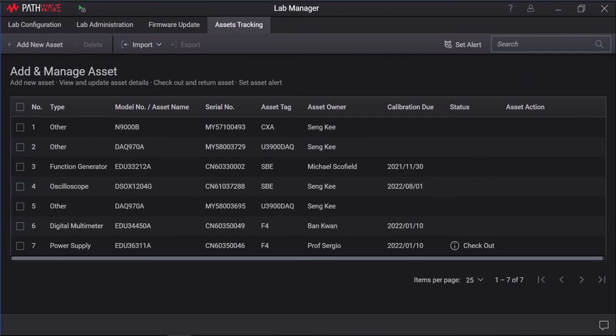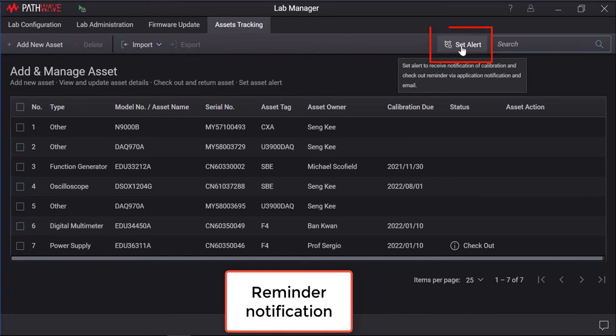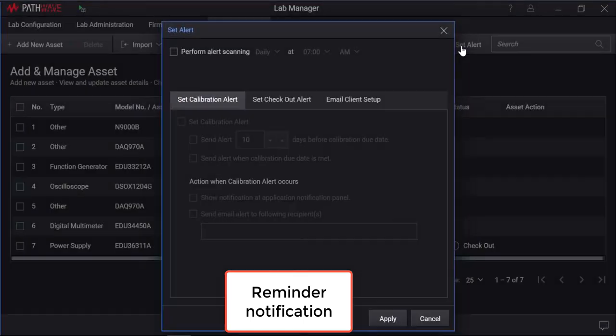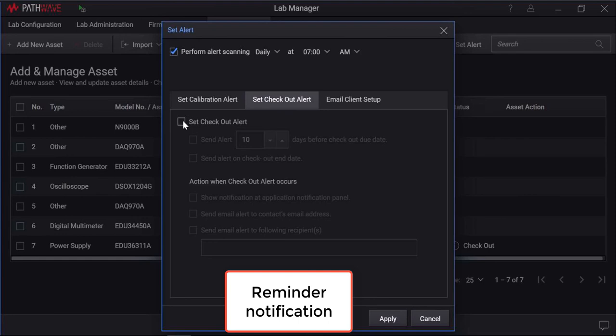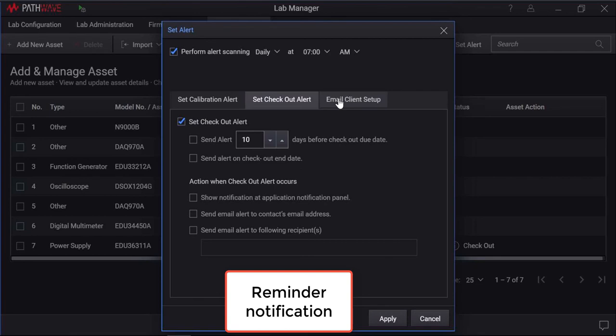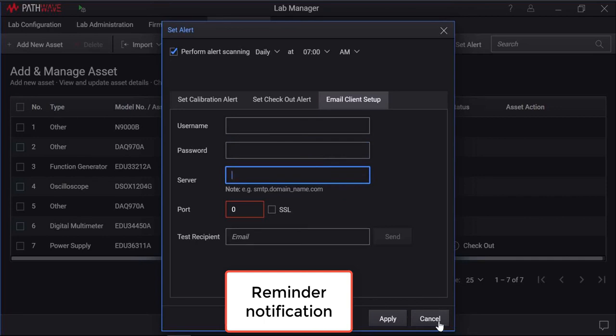The PathWave Bench Vue Lab Manager provides automatic reminder notifications for instrument calibration's due date and asset checkout end date. The reminder notification settings are customizable according to the user preference. Click on the set alert and you may customize how often and at what time the system performs reminder scan on the lab assets for calibration notifications or asset checkout reminder. You may also choose to send an email notifications to the recipients.